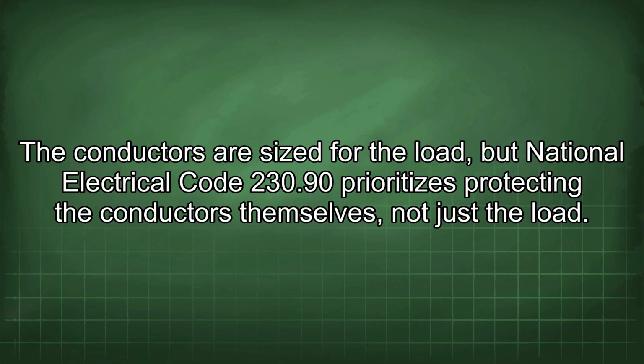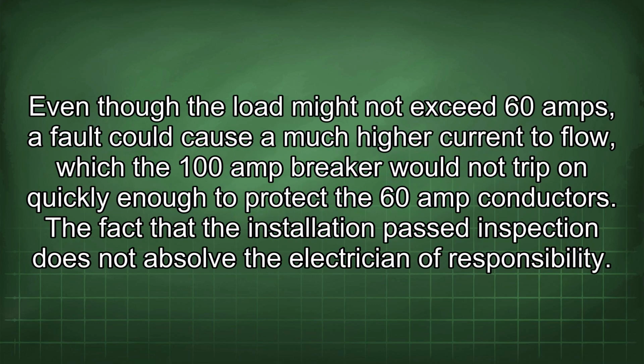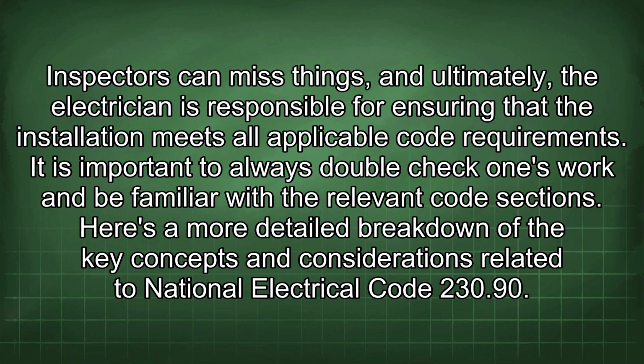The conductors are sized for the load, but National Electrical Code 230.90 prioritizes protecting the conductors themselves, not just the load. Even though the load might not exceed 60 amps, a fault could cause a much higher current to flow, which the 100 amp breaker would not trip on quickly enough to protect the 60 amp conductors. The fact that the installation passed inspection does not absolve the electrician of responsibility. Inspectors can miss things, and ultimately, the electrician is responsible for ensuring that the installation meets all applicable code requirements. It is important to always double-check one's work and be familiar with the relevant code sections.